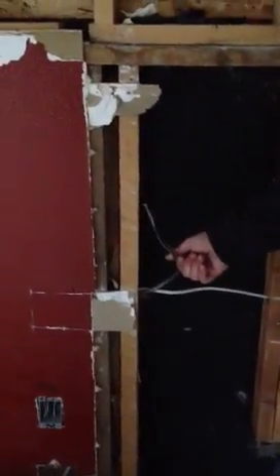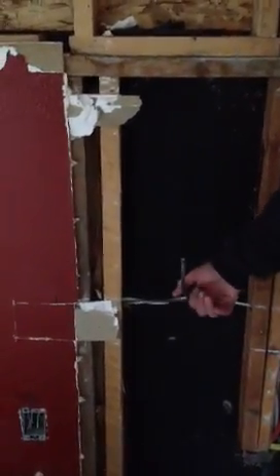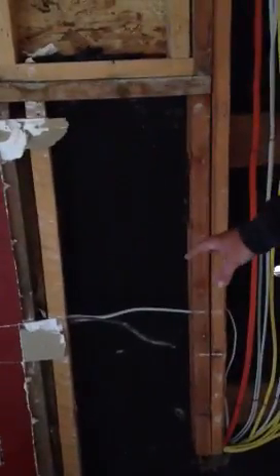That was one of the correction notices. When I pulled the insulation out yesterday, I have no idea what that wire is for. You were supposed to take all abandoned wires out — all abandoned wires need to be taken out. I don't know what dad's doing. If he picks that up somewhere, that could be very dangerous.